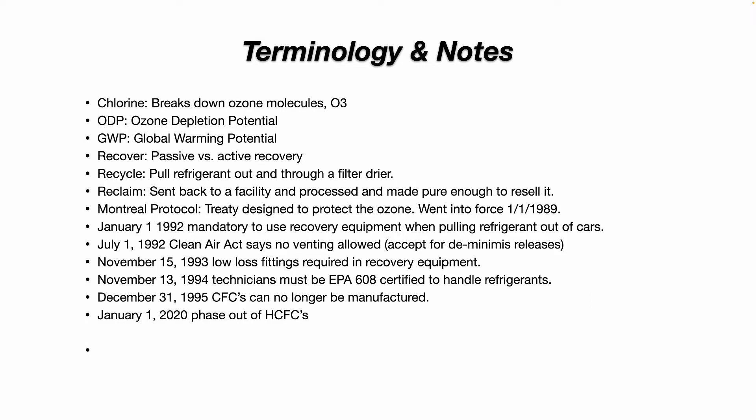November 15, 1993 requires low-loss fittings on all recovery equipment. November 13, 1994, technicians must be EPA 608 certified to handle refrigerants. December 31, 1995, CFCs can no longer be manufactured. January 1, 2020 was the phase-out of HCFCs.